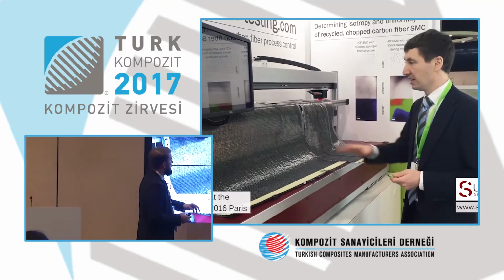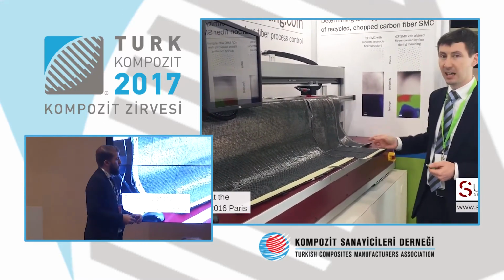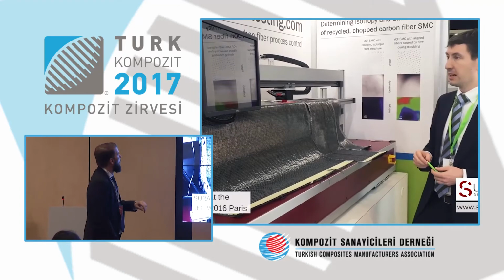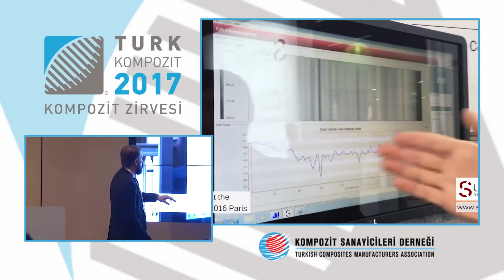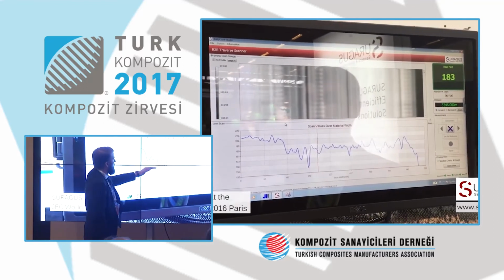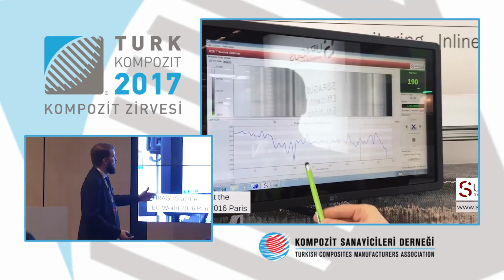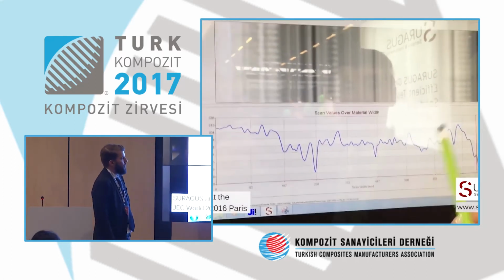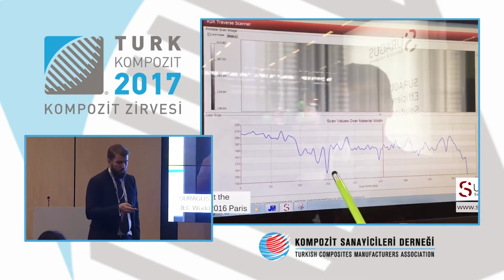You see here that there are, of course, some gaps between the different material. And also we pulled some strands. This is what Richard is just right now explaining. So we pulled some tows, and our system can show that. You see here that in these spots the resistivity is going down, because there's less material. And in that case, we got this very, very strong peak. We can find these defects even when you cannot see them with your eye or a visual inspection system.